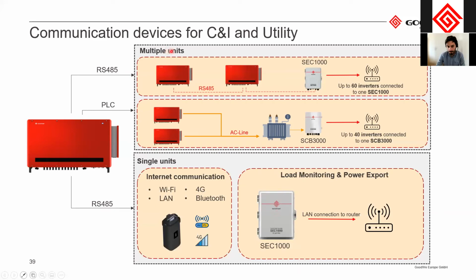To connect multiple inverters, you can choose to use RS-485 or PLC, power line communication. With RS-485, you use the same box as here for load monitoring and power export. This means that you could also achieve load monitoring and power export for several inverter units. To one of these boxes, you can connect up to 60 inverters, and they're all connected with RS-485 between the inverters in daisy chain.